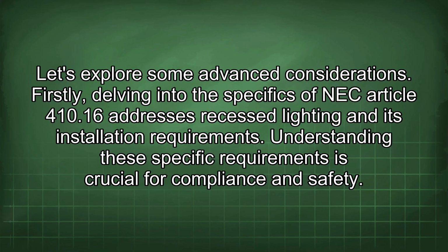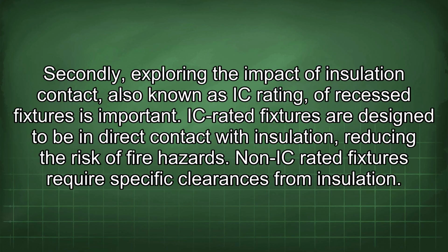Firstly, delving into the specifics of NEC Article 410.16 addresses recessed lighting and its installation requirements. Understanding these specific requirements is crucial for compliance and safety. Secondly, exploring the impact of insulation contact, also known as IC rating, of recessed fixtures is important. IC-rated fixtures are designed to be in direct contact with insulation, reducing the risk of fire hazards. Non-IC rated fixtures require specific clearances from insulation.